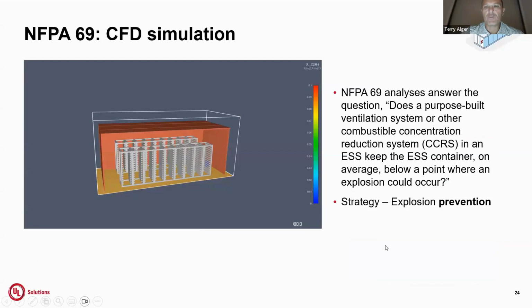So here's an example of a CFD simulation for NFPA 69. The question we're trying to answer when we're looking at these kind of simulations is, does the ventilation system or other kind of combustible gas reduction system, on average, keep the concentration of flammable gases below the point at which an explosion can occur.